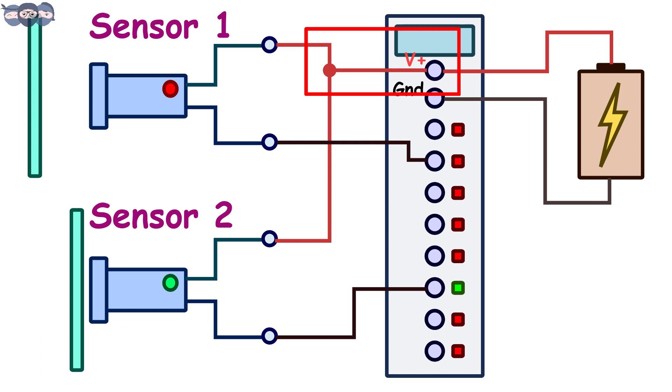In the figure shown, the input module is a sinking type. Here, the V positive of all sensors will be connected to V positive point on the module, and output of different sensors will be connected to the individual points on the input module.